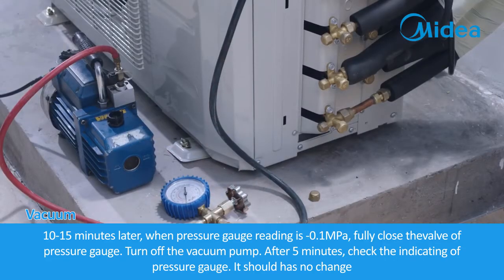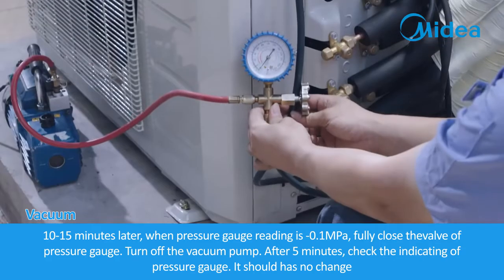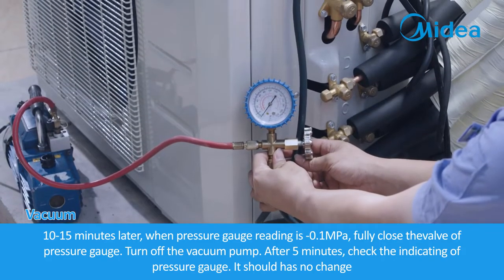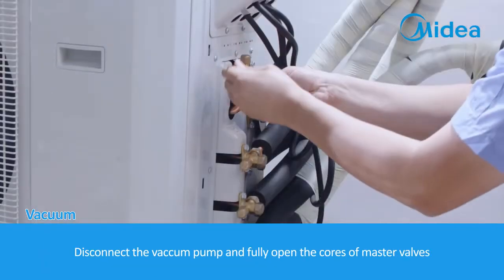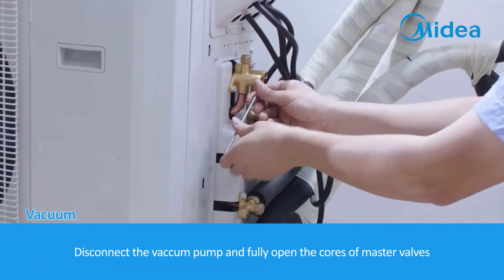After 5 minutes, check the indicating of pressure gauge. It should have no change. Disconnect the vacuum pump and fully open the cores of master valves.